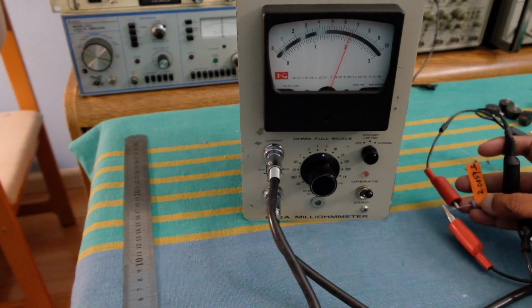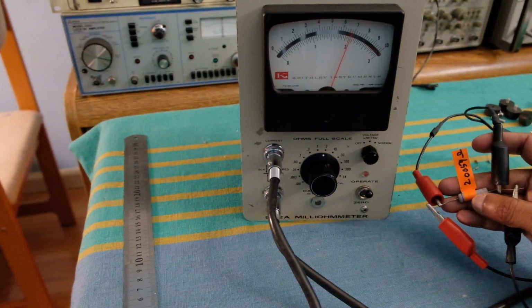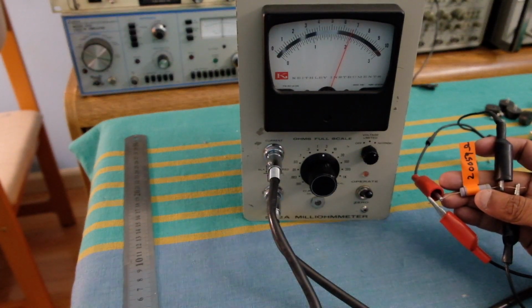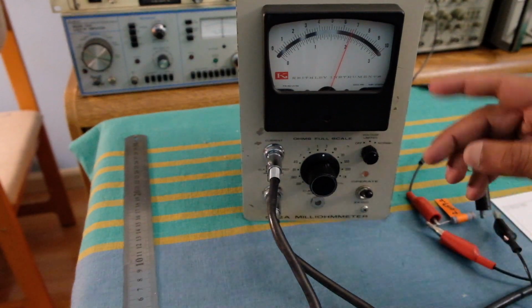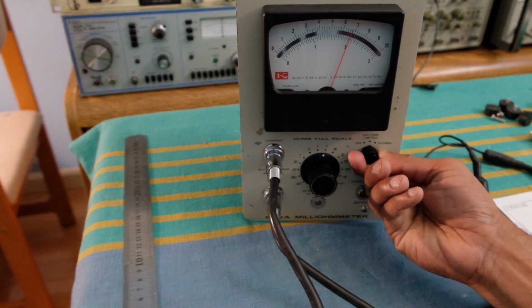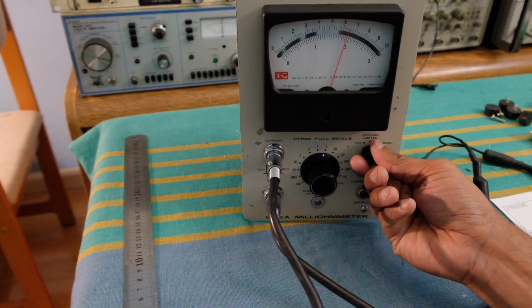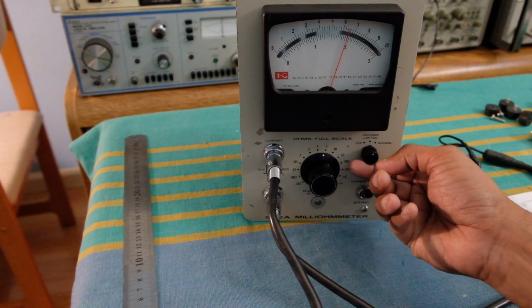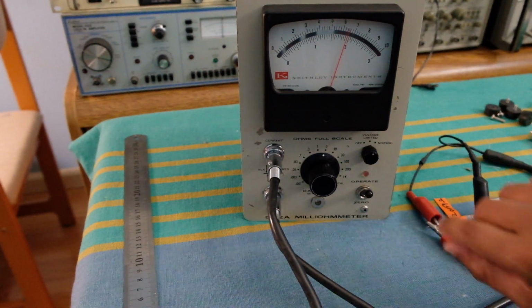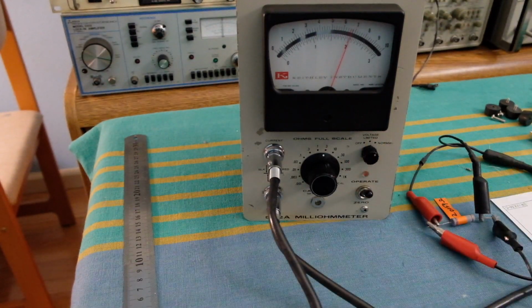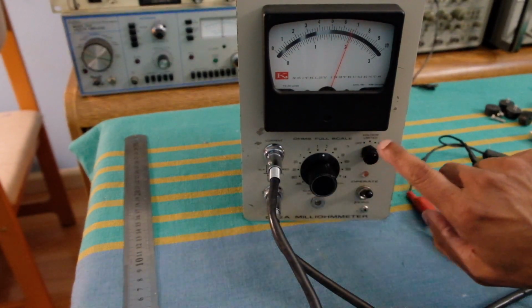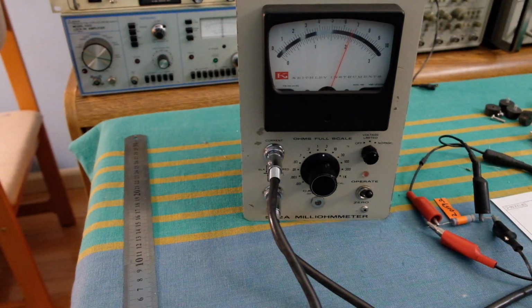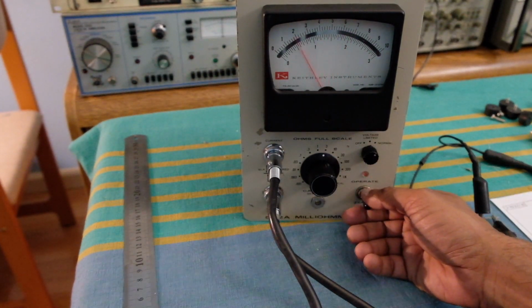And this resistor, I had measured it using my milliohm meter and some other meters at 2.0059 ohms. So I think this reads very well. If I go into the lower voltage limited range, there's a slight error. I think it's okay. When you're using it for certain applications, you're forced to use that, but for most normal operation, it's better to be in this range where it's more accurate. Could probably calibrate that out, but that involves adjusting one of those bypass resistances, which in this design is not programmable like in the other older version of this instrument. So that's the 2 ohm resistor.